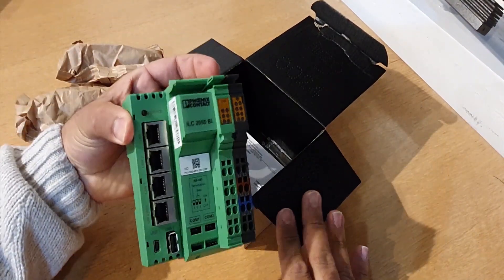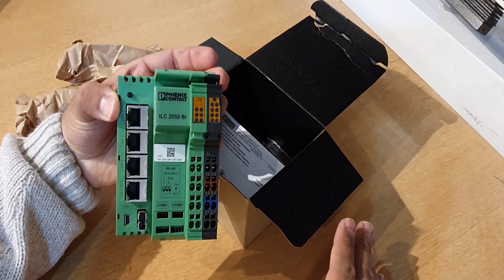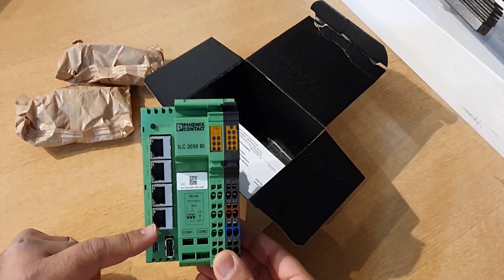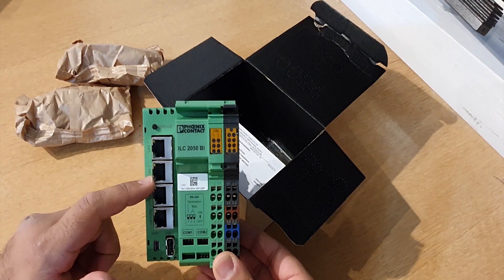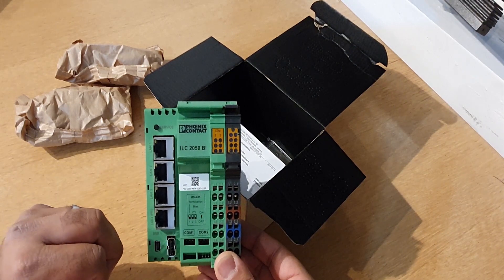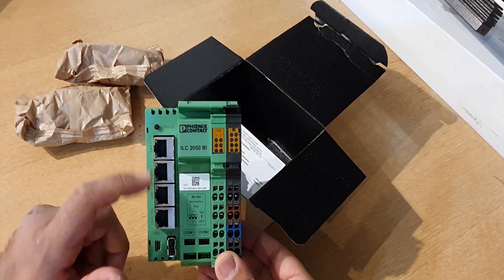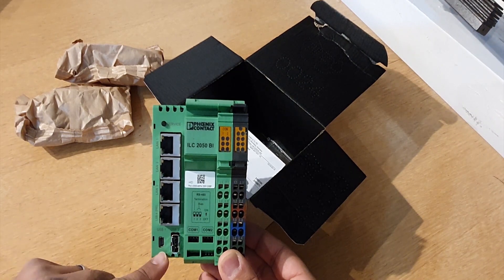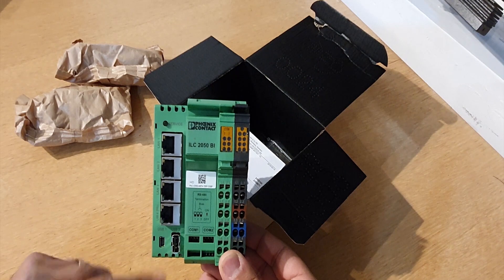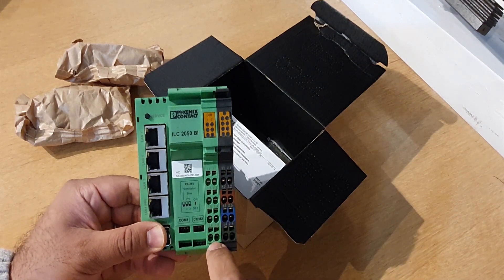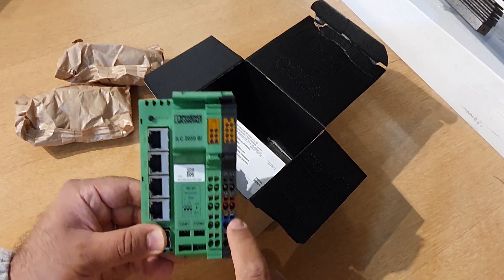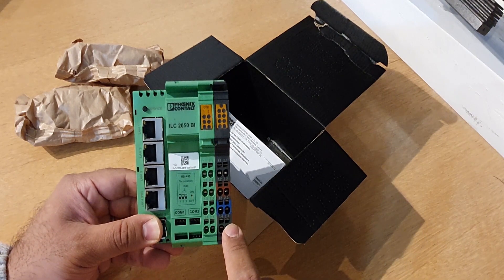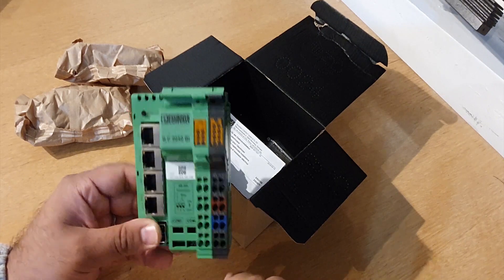Here's the ILC 2050 BI controller. You have four Ethernet ports, where each two ports has a network card, so there's two network cards on the board. You have a diagnostics port here. You've got two RS485 ports. And then this one here you use to power 24 volts DC to power the controller.